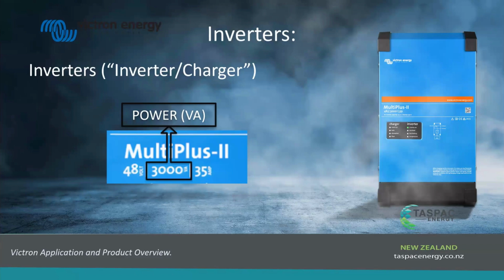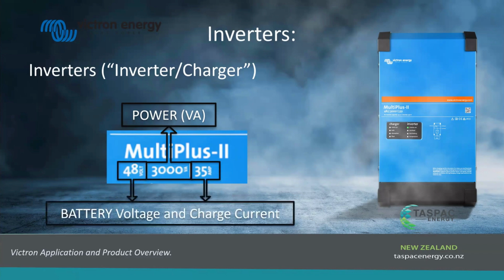It will overload to a good 6000 watts for probably something like 5 to 20 seconds, again, depending on temperature. But they've got a huge surge capability, and it will overload to maybe 3 times its rated current for a split second while a motor starts. Now, the other two numbers either side of that, 48 volts is the battery voltage. So that's the voltage of the battery. We only carry 48 volt inverters.